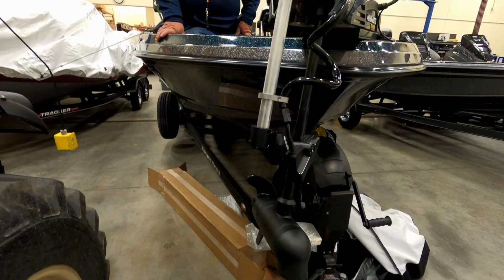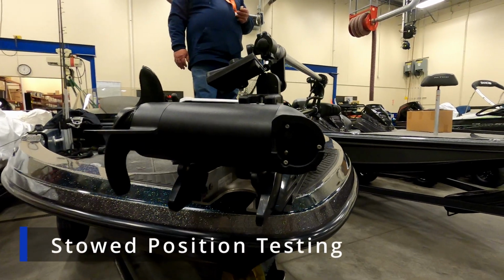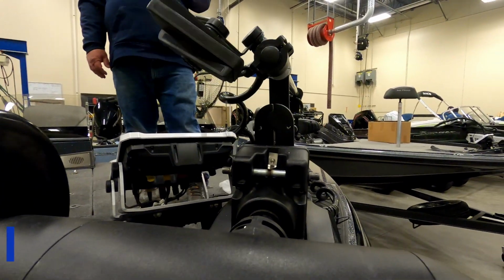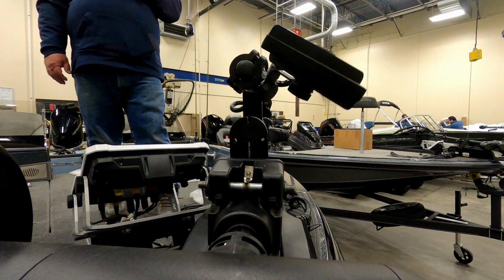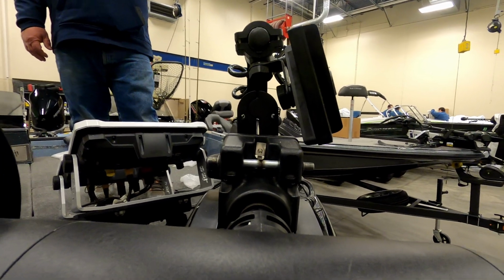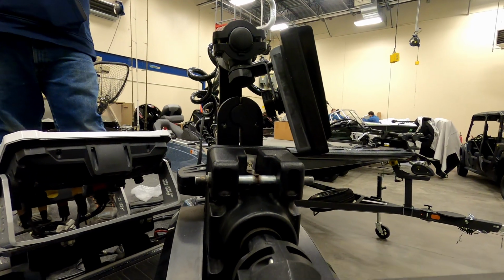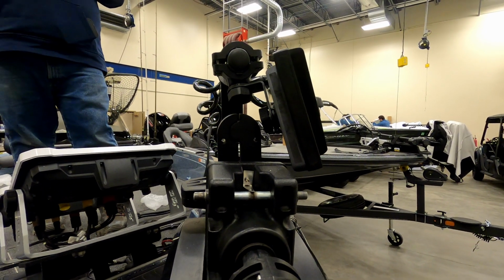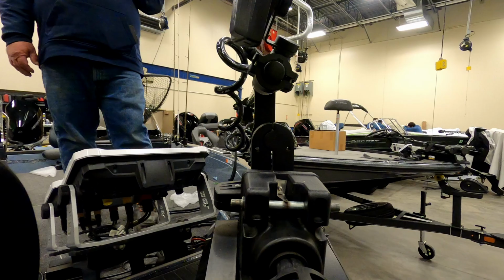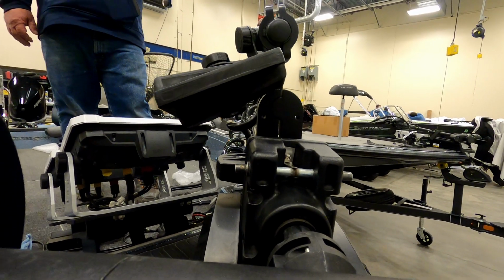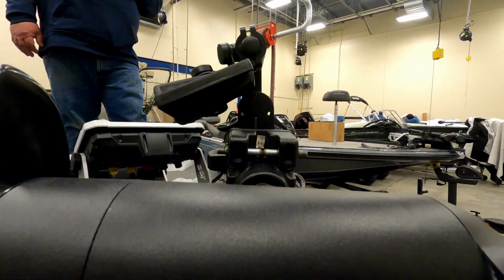The very last thing is I want to check it in the stowed position, to make sure that if he accidentally hits the movement buttons on the live sweep, it's not going to hit anything or break anything. See, when it comes down, it's a little tight on this side. See it move just slightly. So you want to check all those clearances.